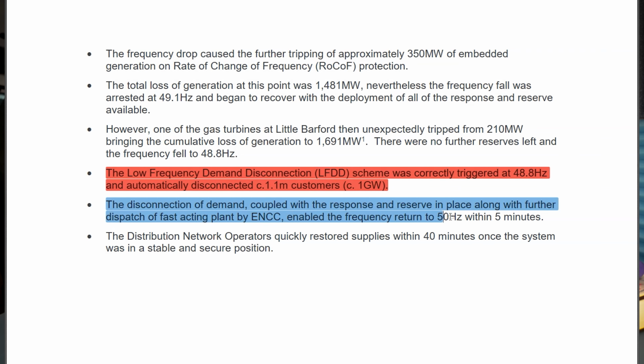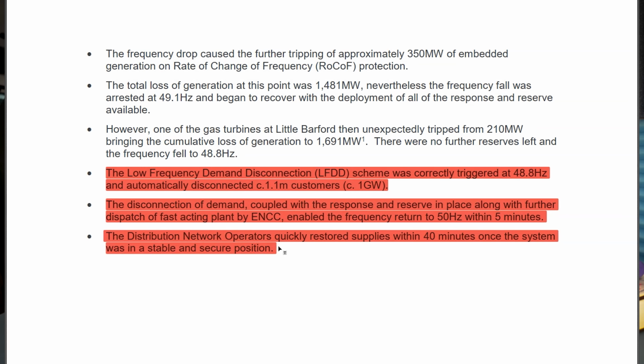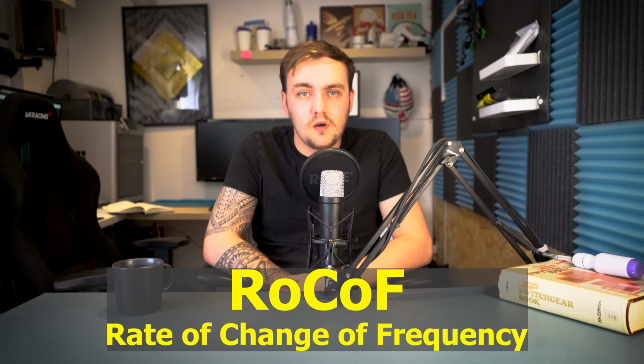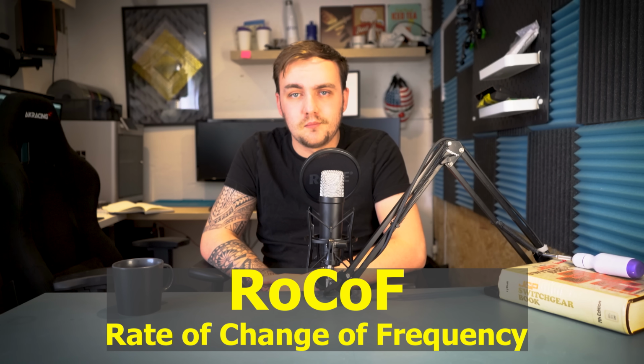Thanks to LFDD acting fast, the grid frequency stopped falling and began recovering. Within 5 minutes, frequency returned to a stable level of near 50 Hz, and over the next 40 minutes almost all customers were reconnected. It's not just how low the frequency gets that matters though, it's how fast it's changing, and that's where another protection setting comes in, RoCoF, or rate of change of frequency.